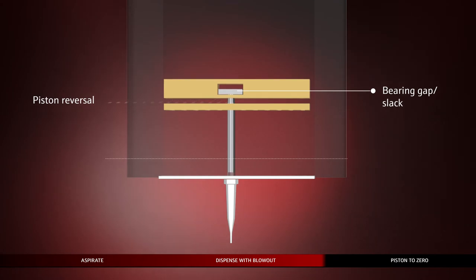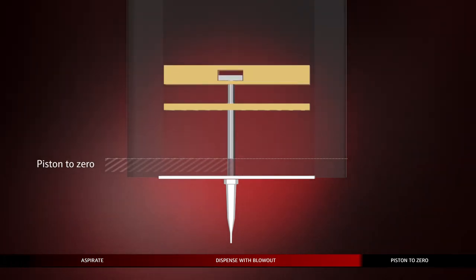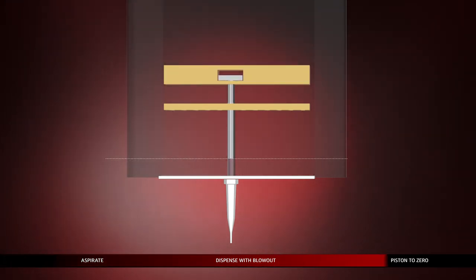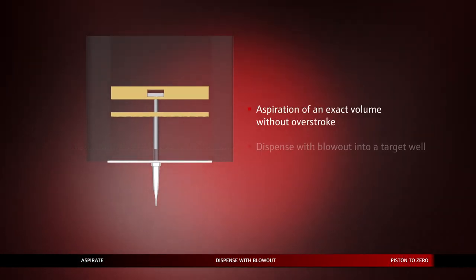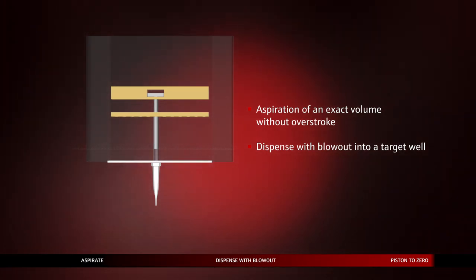At the end, the piston system needs to be reset to be ready for a new pipetting cycle. The pistons move back to the starting position, also known as piston to zero line, so that the system is prepared for the next aspiration step.